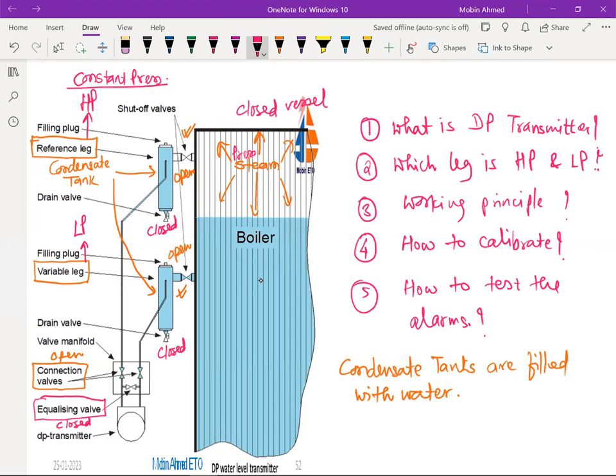Now, because here the valve is open and this boiler drum level is changing, going up and down, this is a variable leg, it is a low pressure, and this is a variable pressure. So this pressure is going to be always variable.